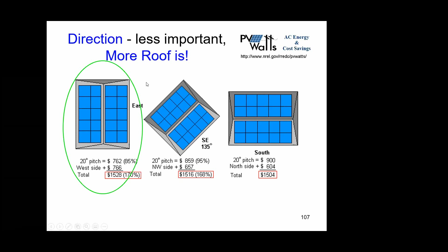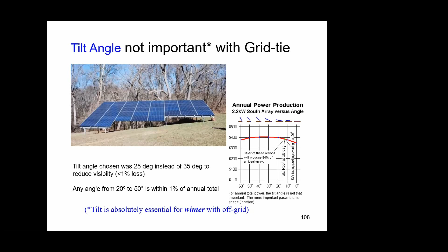Now, the next thing is tilt angle. Again, you don't see erector-set structures anymore to get the exact ideal sun angle, because what matters over the year is total production. Panels can be anywhere from 20 to 50 degrees and the difference is only 1%. At my church, we lowered the array from 40 degrees, which is ideal for this area, down to 25 degrees, and stayed within 1% of total energy production, but the array doesn't stick up as much. So tilt angle doesn't matter that much either.